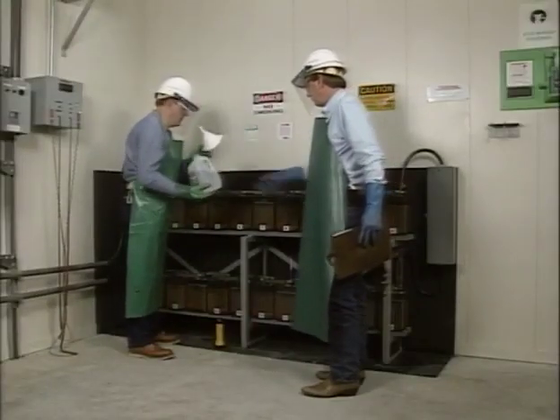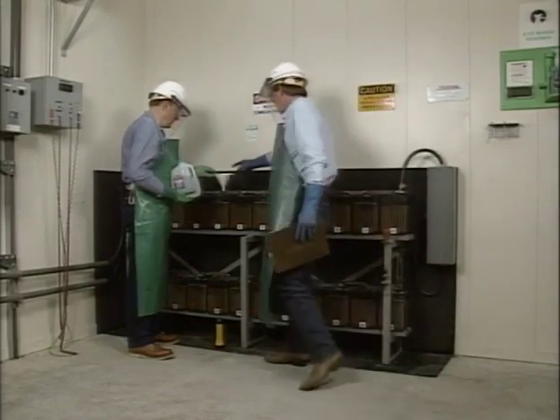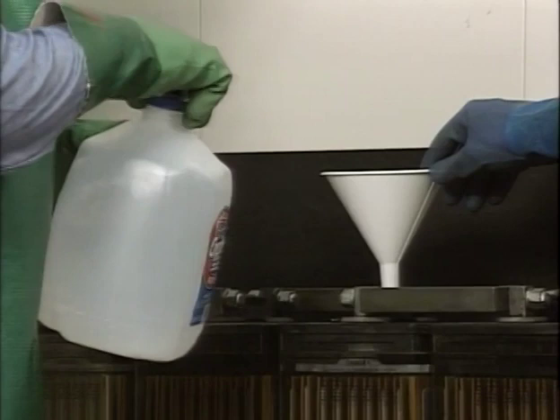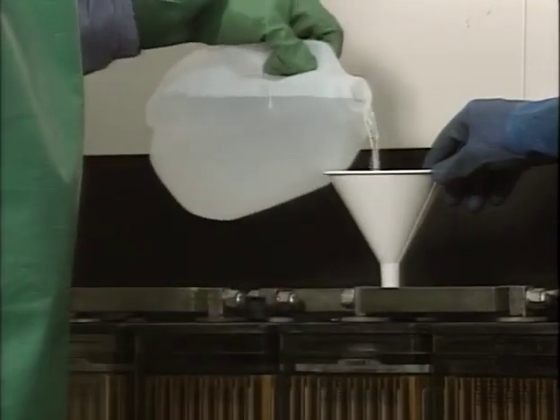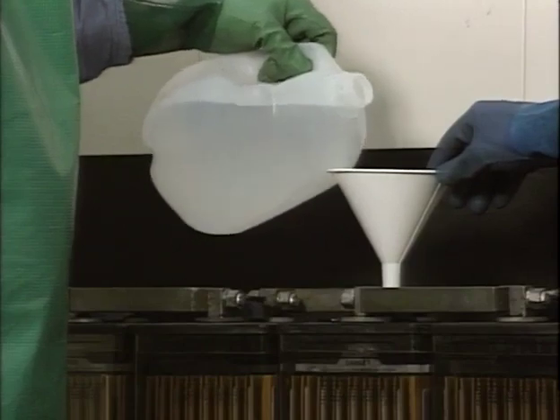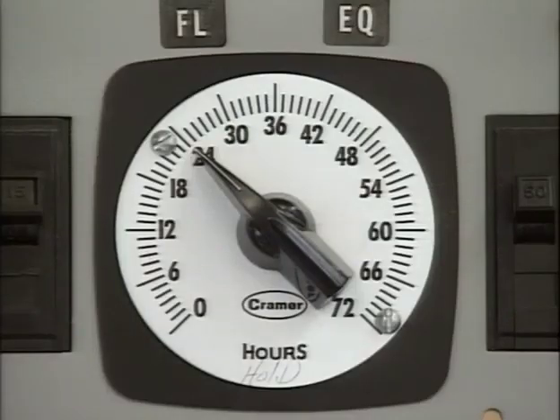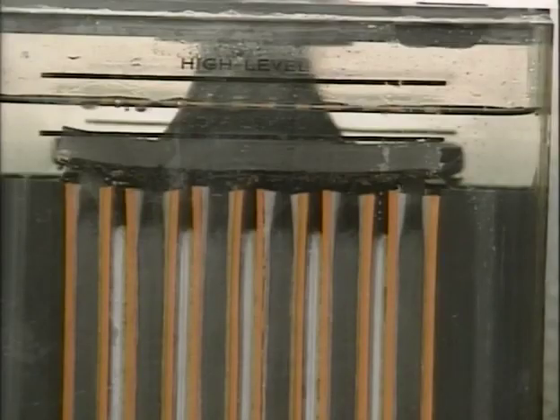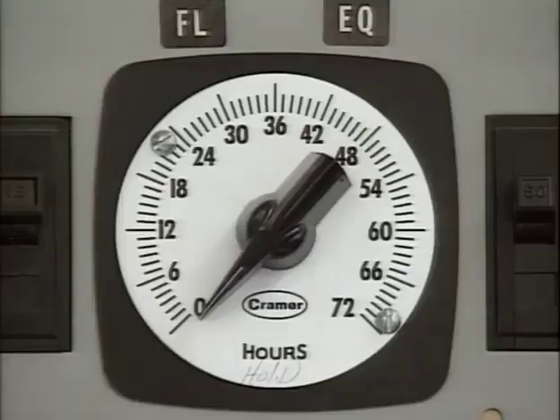Specific gravity should be checked before water is added to a cell because the water doesn't immediately mix with the electrolyte. Under normal float charge conditions, it may take 6 to 8 weeks for the water and electrolyte to thoroughly mix. In addition, specific gravity readings should not be taken during or immediately after a battery is given an equalizing charge. The reason is that it takes time for the sulfuric acid from the plates to mix with the electrolyte, so the specific gravity will continue to increase for a period of time after the cells have been fully charged. For this reason, specific gravities should not be checked until the battery has been on normal float charge for at least 72 hours after an equalizing charge.